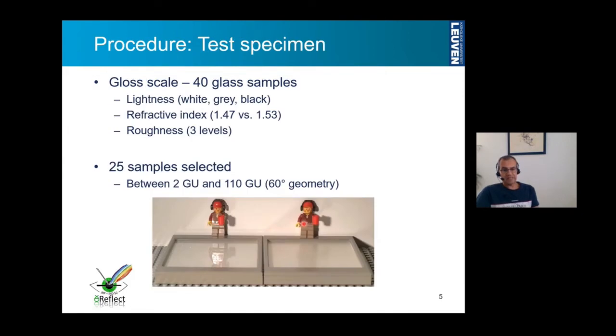Besides instruments, we need samples to do the measurements. Within the project, a gloss scale was manufactured consisting of 40 glass samples. This was done by ECNAM in collaboration with Saint-Gobain. These glass samples differed based on three different parameters: the lightness — white, gray and black samples — the refractive index of the glass samples, and the roughness, where three roughness levels were applied to get a different glossiness range. From the 40 glass samples, we took out 25 samples based on a visual inspection on the uniformity of the reflection and the gloss of the sample, and their gloss values spanned a range of 2 to 110 gloss units in the 60-degree geometry.